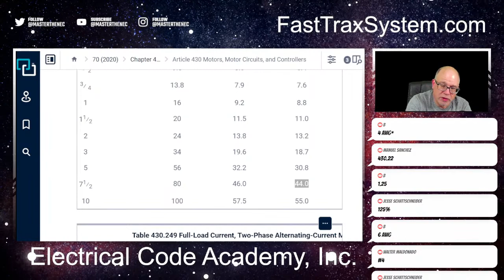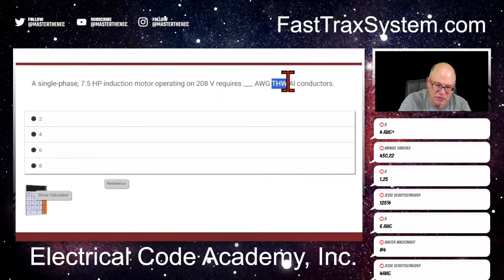The tables are in 430.248, 249, and 250. But don't forget, if it's DC, there is a table 247 as well. And don't forget that this is aluminum conductors. So in our case, we had 44 amps. So we'll go 44 times 1.25, and that is 55 amps. Now what table gives us the ampacities? And remember, this is THW. We're dealing with aluminum THW, so we have a conductor that's good for 55 amps, it's aluminum, and it's got to be THW. Just wanted to make sure that is all clear.